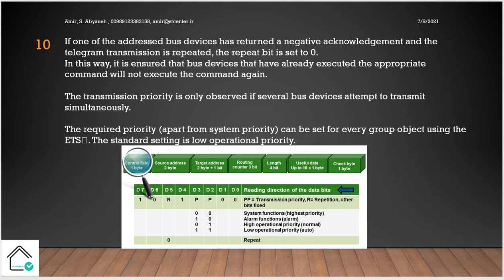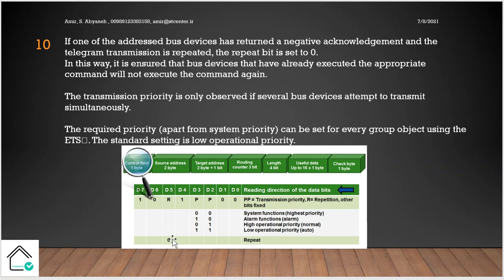So you remember we talked about this concept that if the sender does not receive the acknowledgement, it sends again. In this case, maybe the sender sends the telegram to different devices, different group addresses. So some of them already got it. So when they got the repeated telegram, some bits are changed in the control field. So the ones who receive the telegram and execute it, they do not execute it anymore. You can see in the picture one bit is set to zero, so it means this is a repeated telegram.